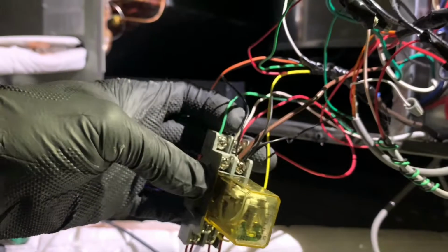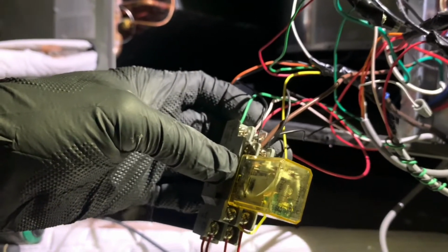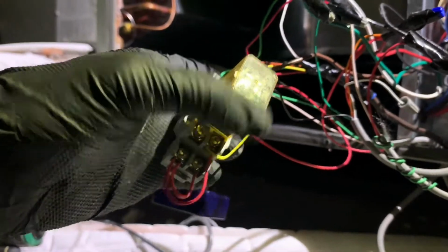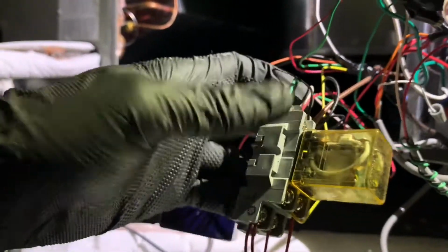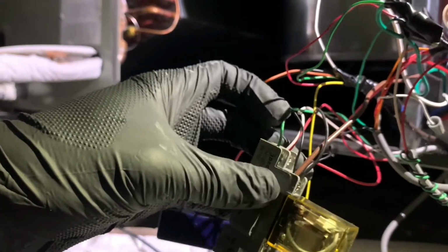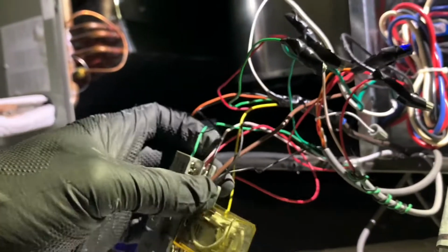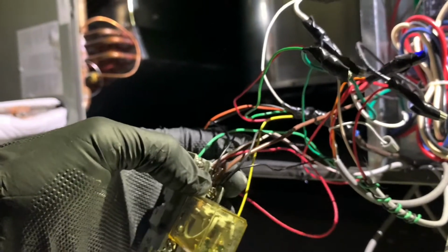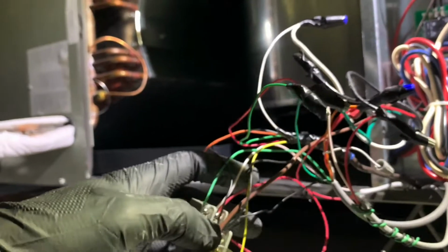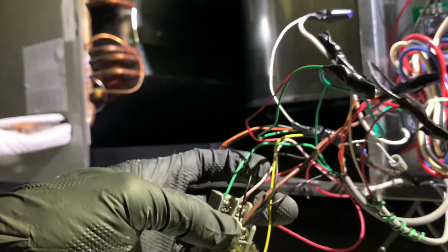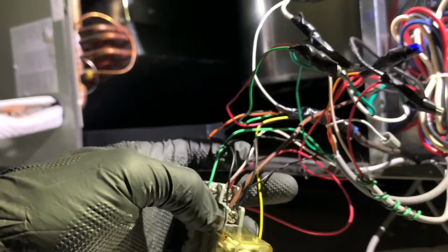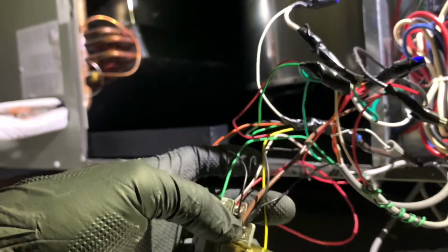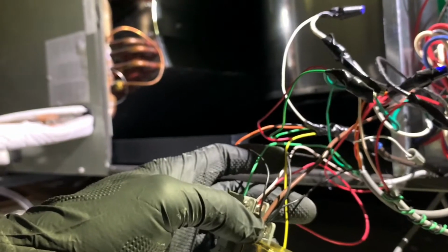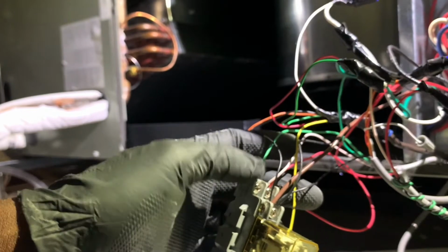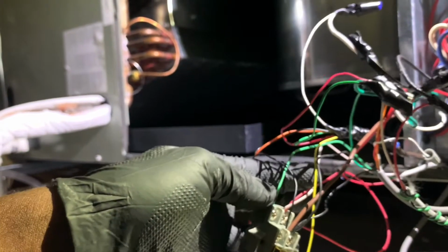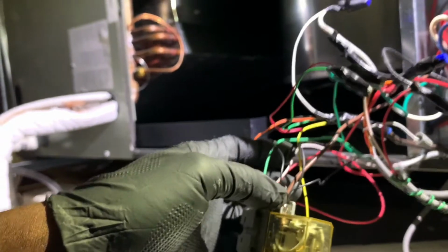So now this green wire here, because it's a heat pump, once there's a cooling signal, it activates the relay, closes these contacts between here and here, and then this green wire gets 24 volts. That goes to my reversing valve with my condenser unit, outdoor unit. And then this white wire here goes to the cooling, or Y1, or Y, on the condensing outdoor unit. So now, when I call for cooling, I have 24 volts here, 24 volts here, and the white wire goes to my Y, and so I've got the cooling mode on the condensing unit.